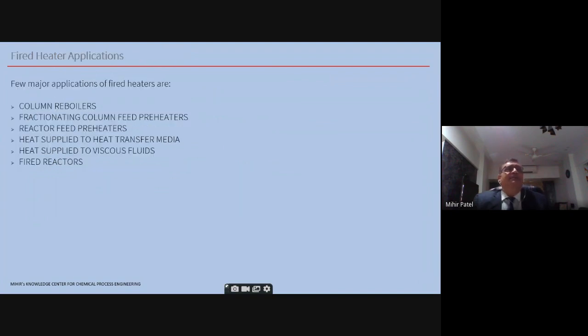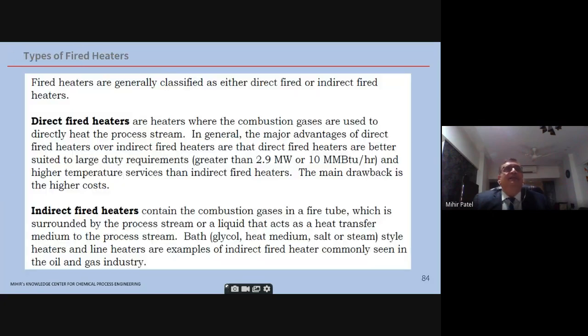Fired heater applications, as you can see, are of many types: column reboilers, fractionating column feed preheaters, reactor feed preheaters, heat supplied to heat transfer media (hot oil heaters), and heat supplied to viscous fluids. Let's say a storage tank farm is there and you need to keep the fluid at a certain viscosity, so you have a fired heater there also. Fired reactors are there too. Now, two types of fired heaters: the direct fired heaters, which you normally encounter in the process industry, where the process coil is directly inside the fired heater and you are heating with direct burning of the fuel. And the indirect fired heaters.